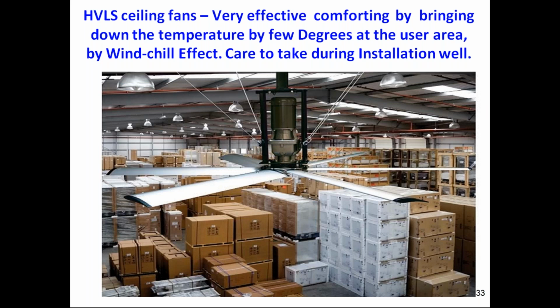This is where we find what we call the Pareto principle, where 20% of the consumers affect the 80%. So especially on the air conditioning system, if you are able to concentrate on the fans, definitely this will improve the chiller compressor cutting in and cutting out. Similarly, in typical industries like this, an HVLS fan gives a wind chill effect, and automatically the comfort level for the given environment or premises is made excellent by more fresh air, at the same time recirculation and the wind chilling effect. This is a better proportion we always suggest to the industry after our energy audit.